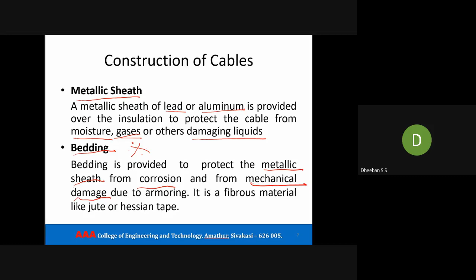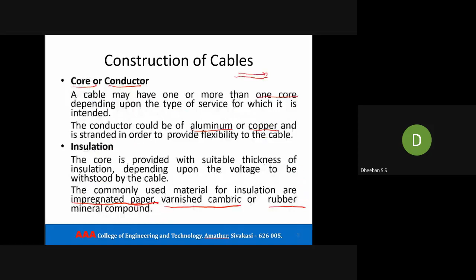Next is the metallic sheath. This metallic sheath will be of lead or aluminum. It is provided to protect from moisture, gas, and other damaging liquids. This is what it looks like, your metallic sheath, and its main purpose is to protect from moisture or gas. Next is the bedding. It is a very important question from the university point of view: what is bedding? They might ask. It is used to protect the metallic sheath from corrosion and from mechanical damage. The main purpose of bedding is to prevent mechanical damage. It is a fibrous material of jute or Hessian tape. Hessian is a kind of material. Here you can see these layers which will come under your bedding.